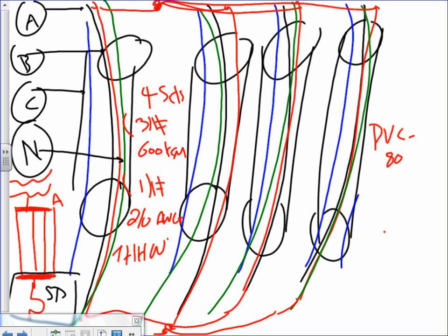Now then, you can use galvanized rigid, but you're absolutely right. They use galvanized rigid. They also use PVC-coated rigid on some of these, but typical. Galvanized maybe was old school and PVC-coated is maybe newer. Like I said, typical engineering projects: when you go underground, guys, you go PVC. You go above ground, you have two options. When you go above ground, you can either use rigid.